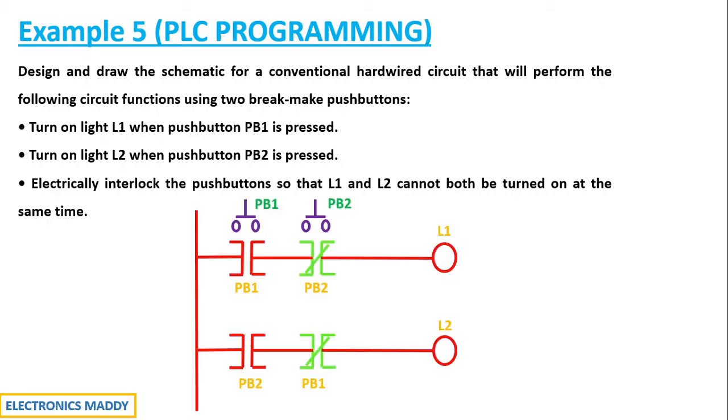So this is the ladder diagram which is quite similar to the quiz problem that we saw with respect to the example in interlocking. Over here if you carefully observe we have two push buttons which is PB1 and PB2 and they are electrically interlocked by using normally closed contacts connected in this particular fashion. PB1 over here, PB1 over here in the second rung with a normally closed contact. This is a normally open contact. Let's do the analysis part with respect to this problem.